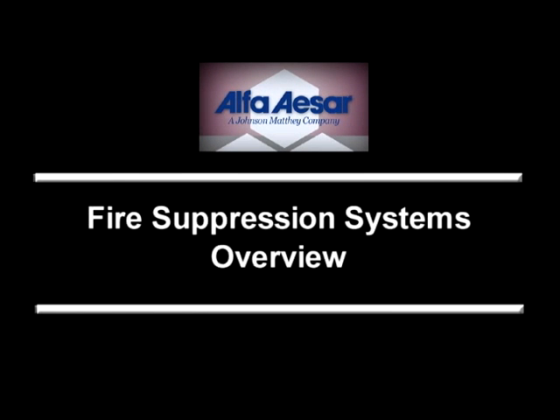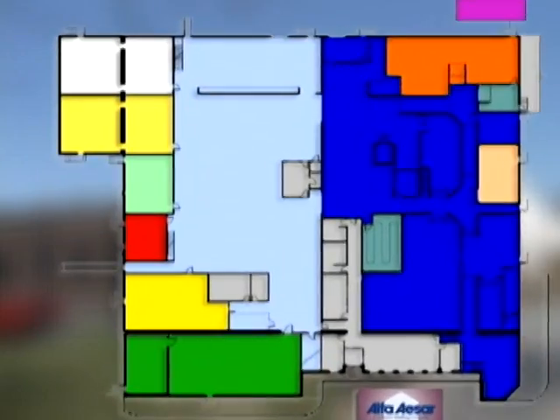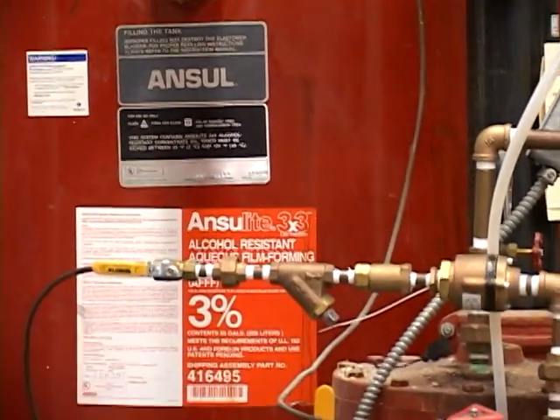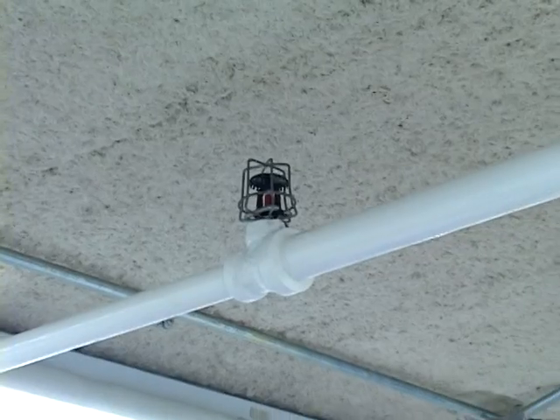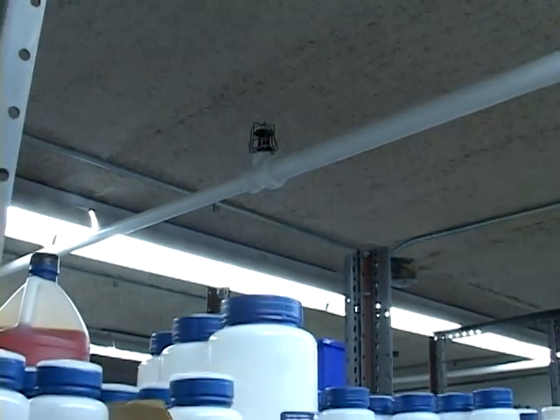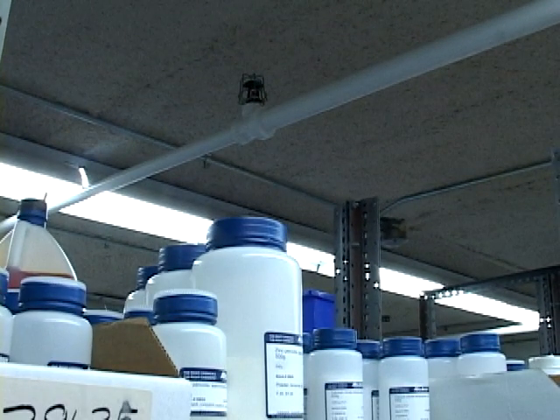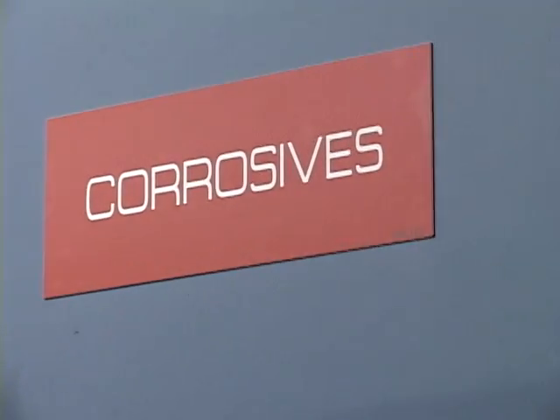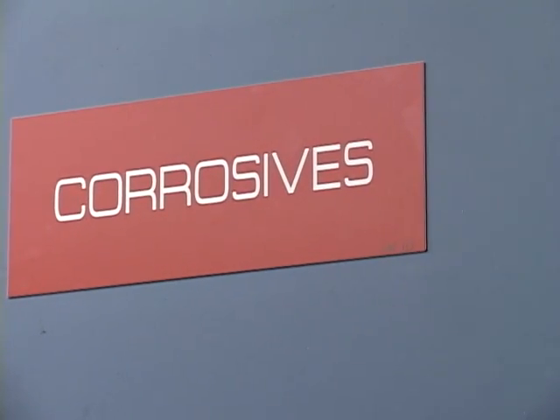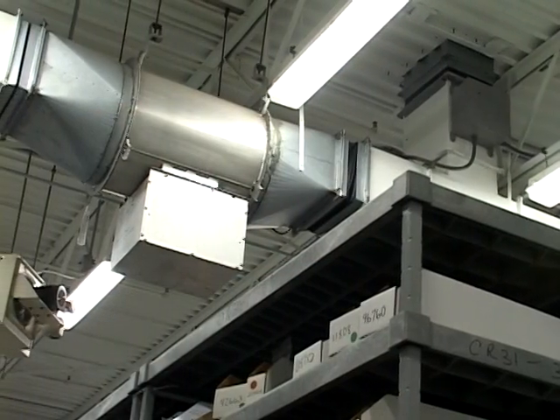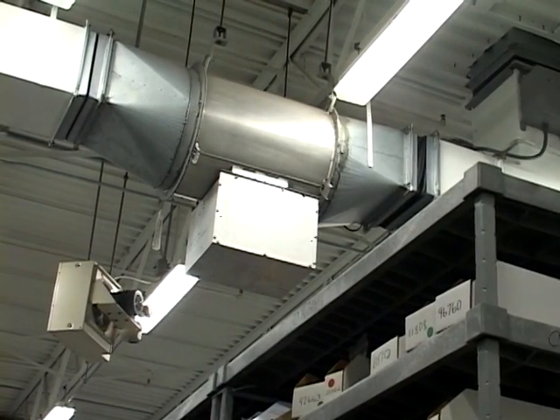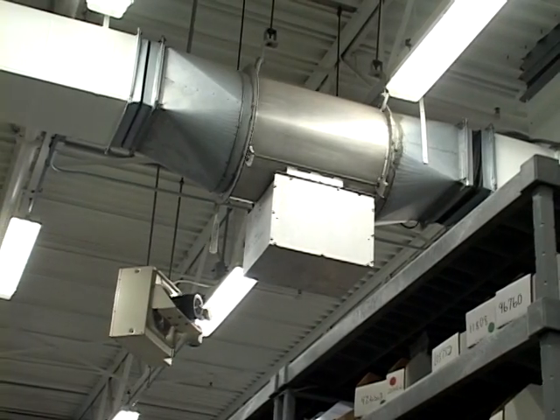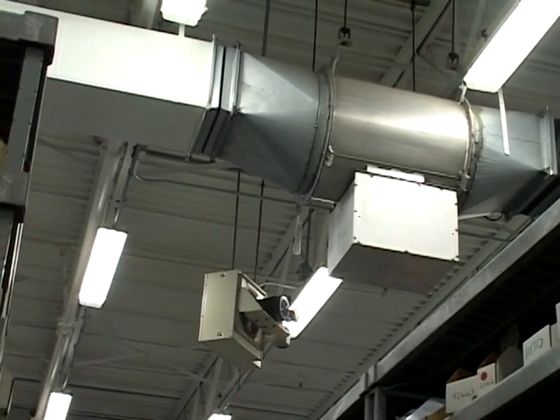Fire suppression systems overview. The facility has complete fire suppression coverage throughout all areas. Systems include an AFFF foam extinguishing system for the flammable liquids storage area and wet pipe sprinkler system protection in other areas. Each hazard room is self-contained with 3- and 4-hour rated walls and doors. The heating and ventilation system is state-of-the-art, allowing air changes and reacting to self-contain any room with a problem and isolating it from the rest of the facility.